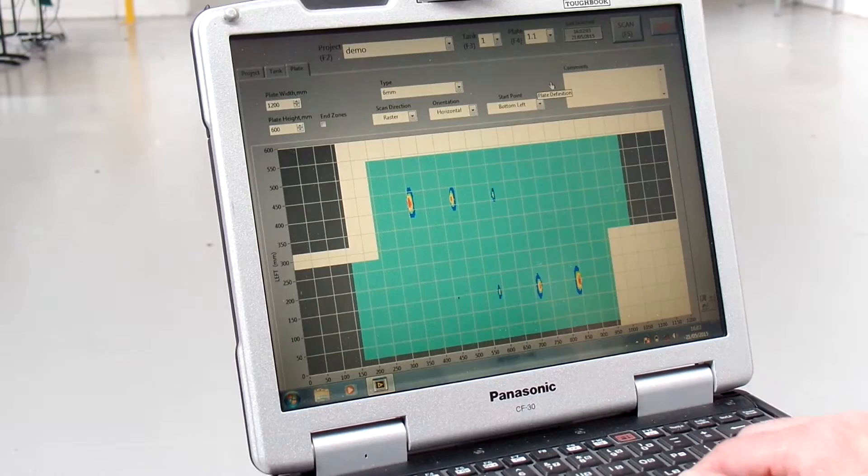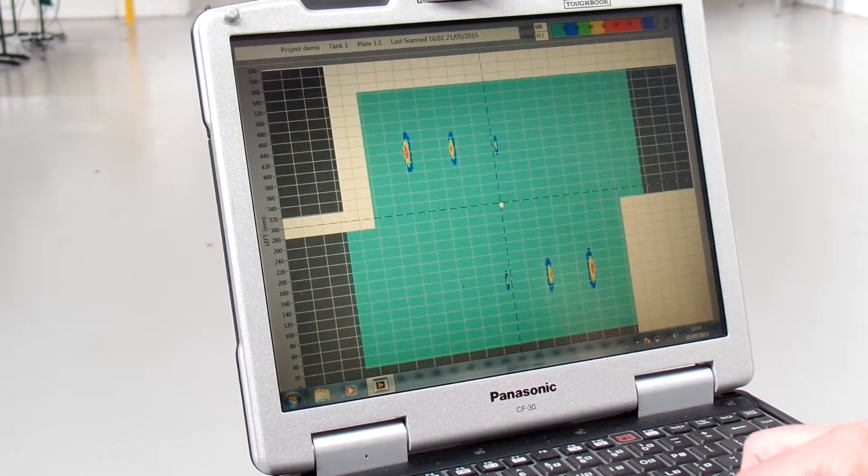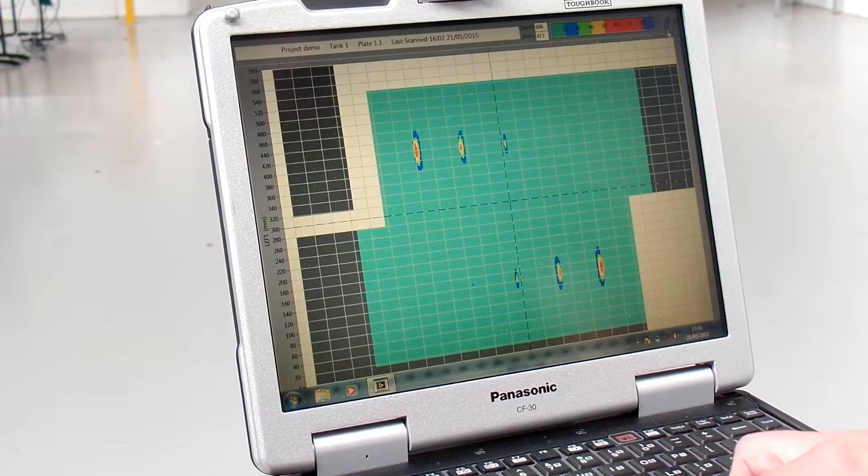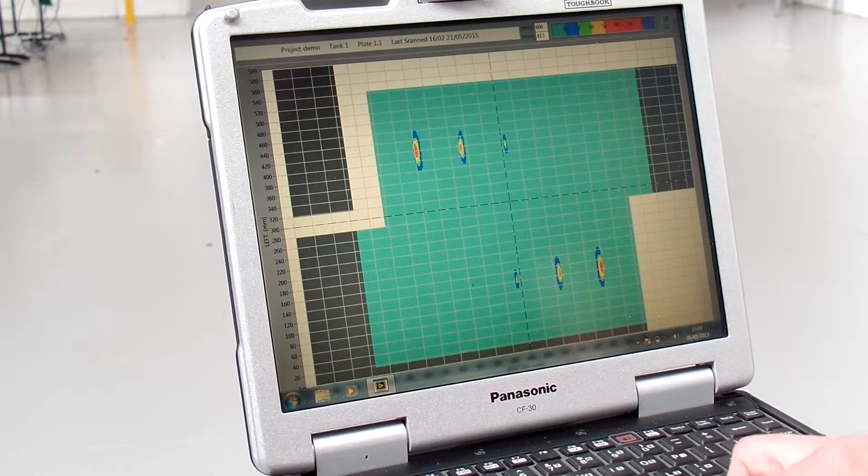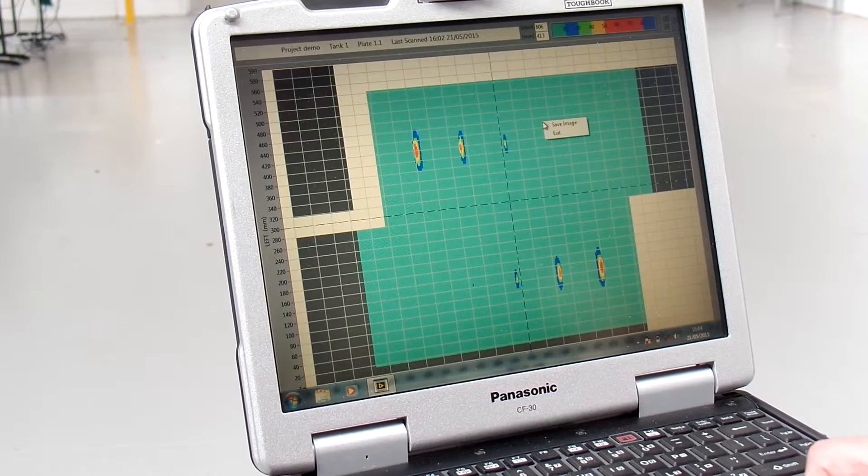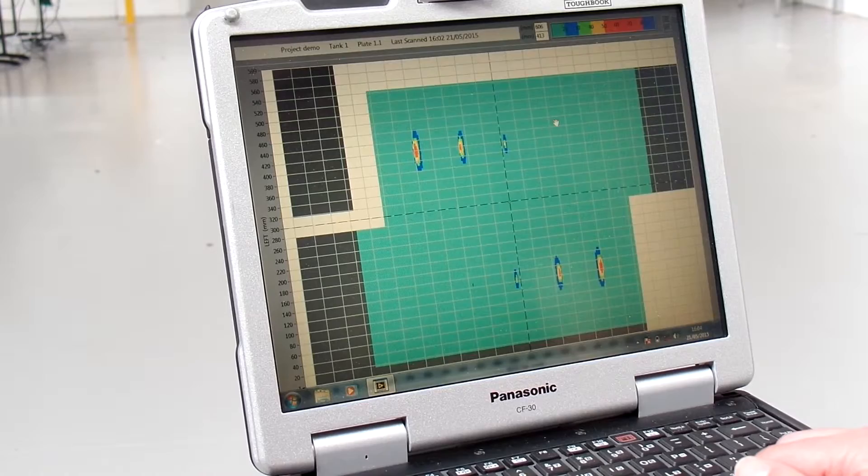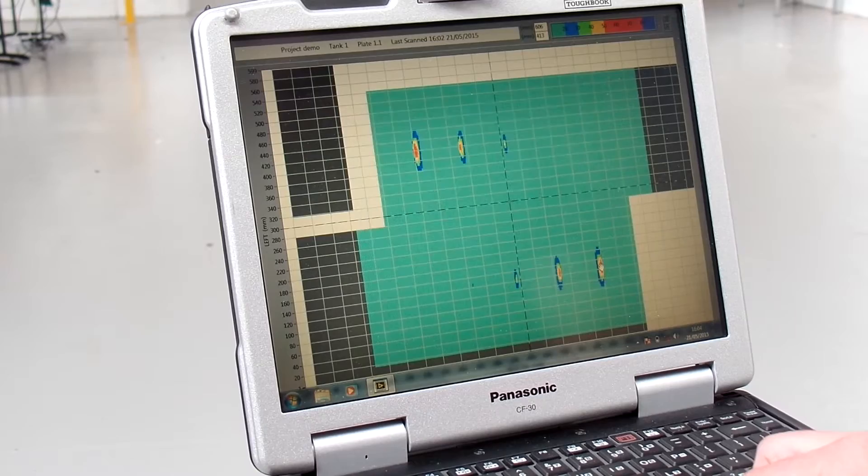To look at the inspection data in more detail, right-click anywhere on the scan and select full screen. You may then move the cursor around or pan the scan. A selection of zoom tools are available from this menu, and a color map corresponding to various through-wall thickness depths are shown on the top of the screen. We can also export the image to file by right-clicking and selecting save image. Or return to the normal view by right-clicking and selecting exit.